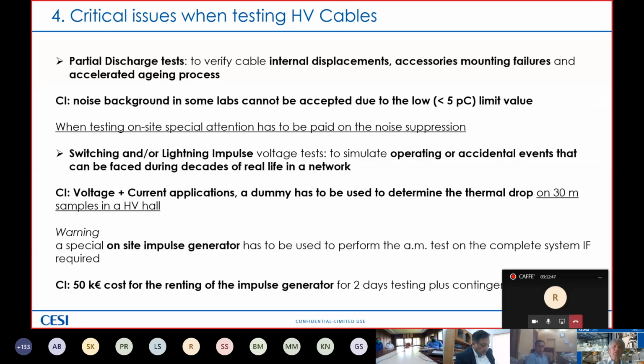There are filters that can be used on site, because in that case there is no fixed value for the background noise. Then after the heating cycles, we need lightning impulses, or switching impulses in case we have a system with nominal voltage greater than 300 kV. These are performed to simulate the operating events or accidental events that the cable system can face during decades of real life in the network.